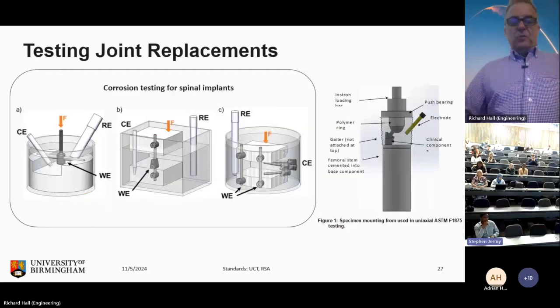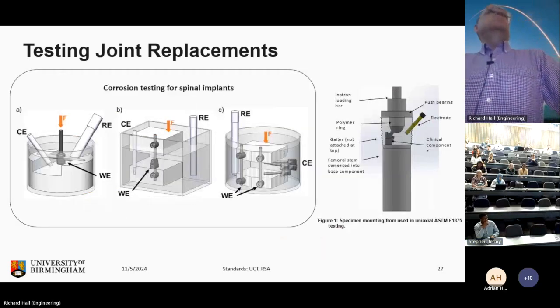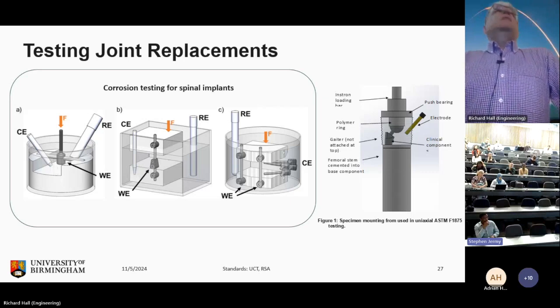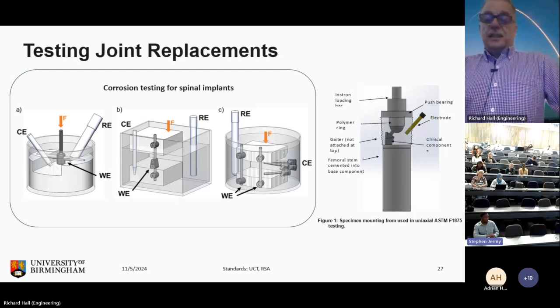And we also do corrosion. Again, there's been an uptick in the identification of failures, both in articulating implants, but also in non-articulating scenarios. And this here is for spinal implants, where metal debris and ions are released due to the fretting corrosion seen in these types of devices. And we can measure the amount of ion release.